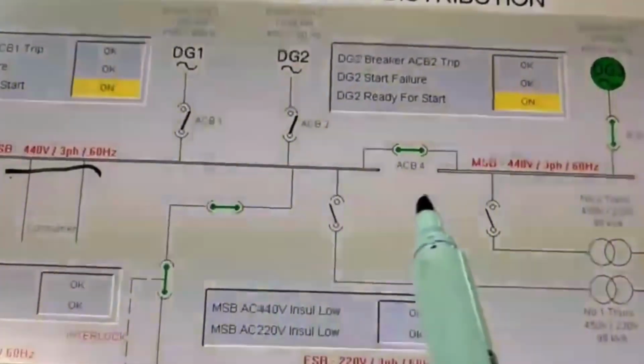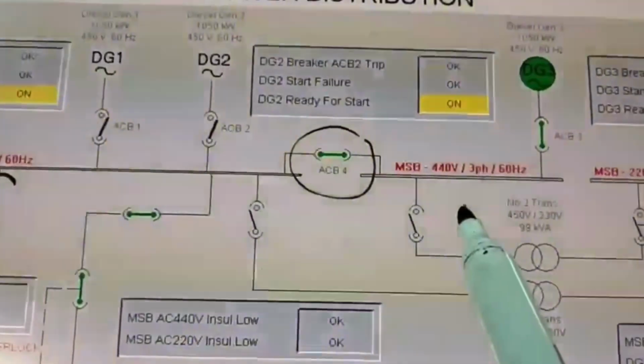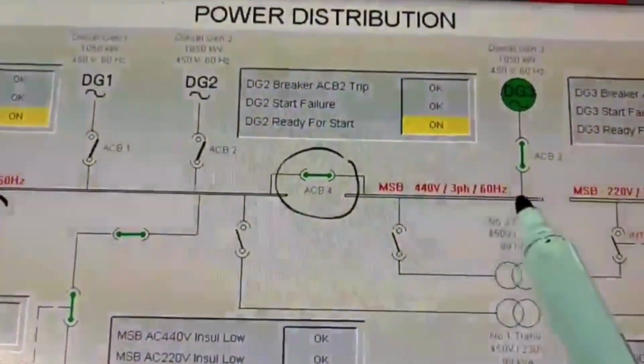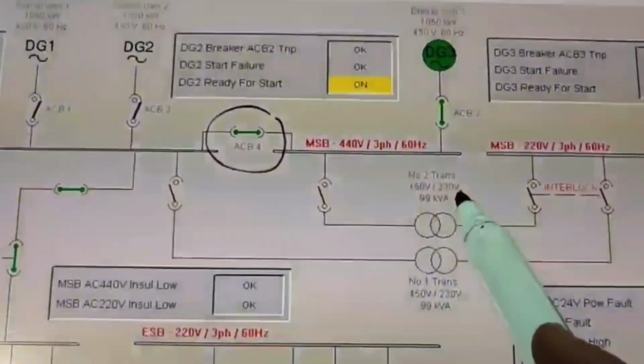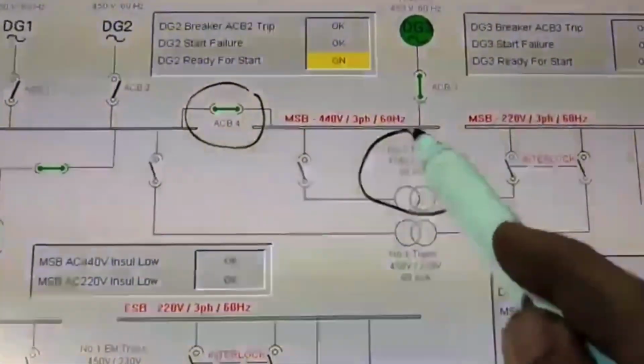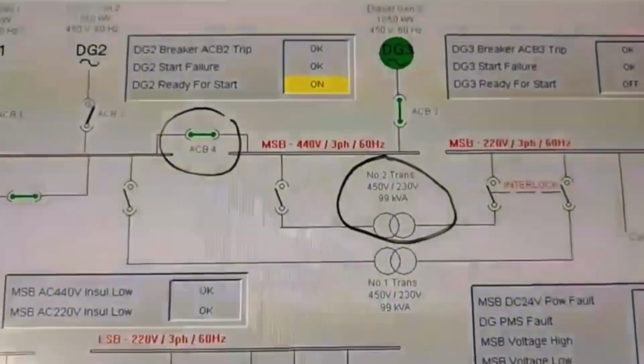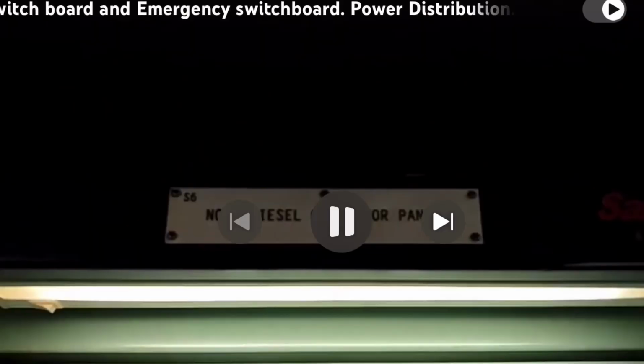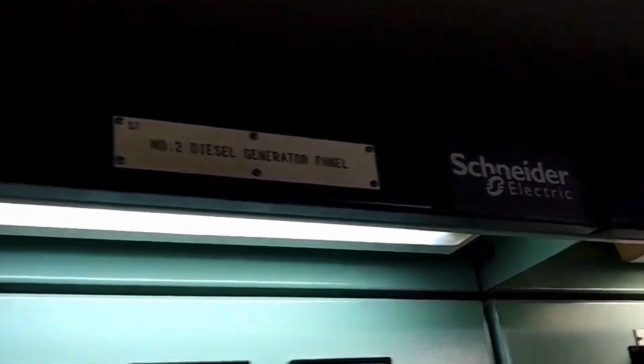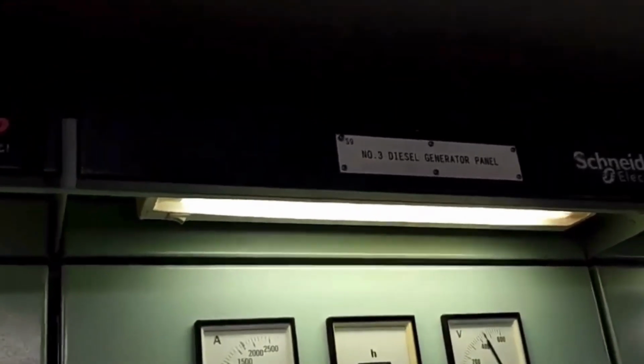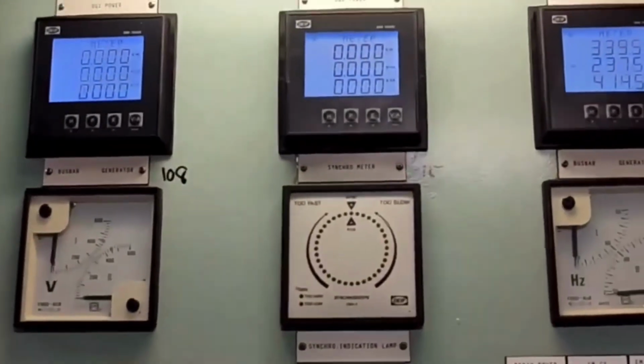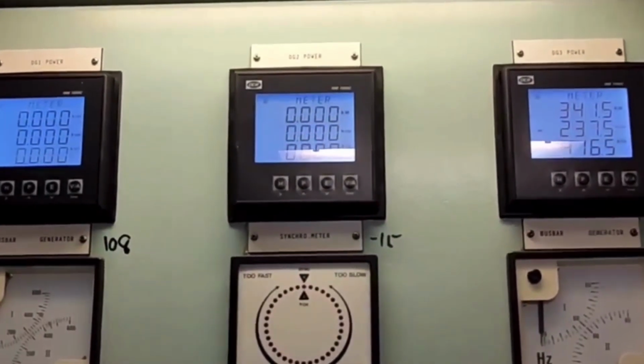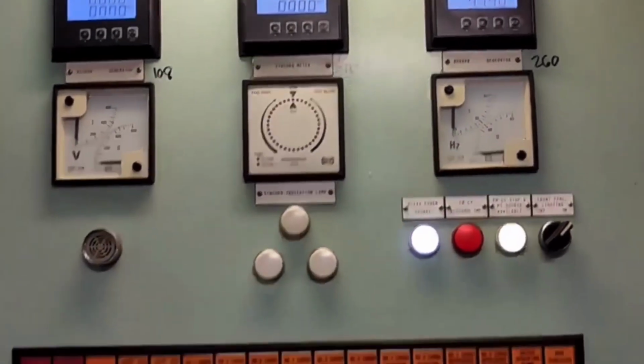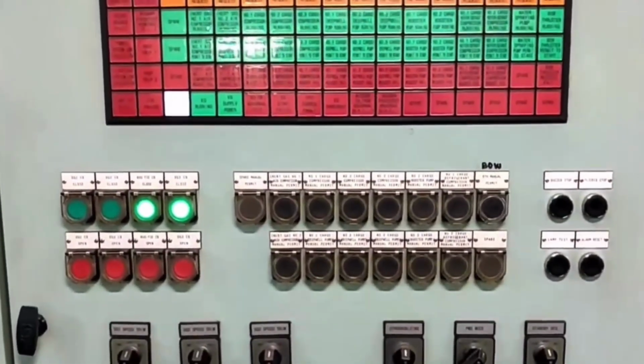High-capacity power cables from the alternator are routed and connected to the switchboard terminals, ensuring secure and properly insulated connections. Every joint is tightened to exact torque specifications to prevent overheating and power loss during operation. Inside the switchboard, the generated power is transferred through bus bars, solid copper or aluminum conductors designed to handle high current loads efficiently. These bus bars distribute electrical power to various sections of the vessel, including propulsion systems, auxiliary machinery, and onboard utilities. Proper insulation, spacing, and support of bus bars are essential to avoid short circuits and ensure safe operation under dynamic load conditions.